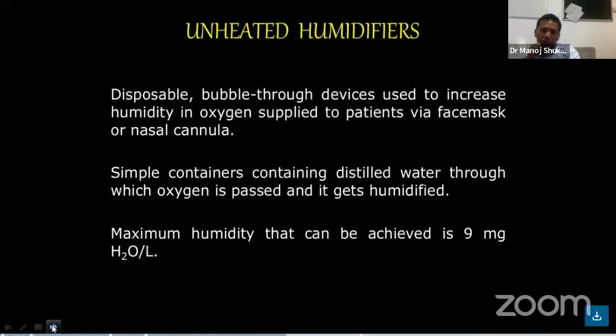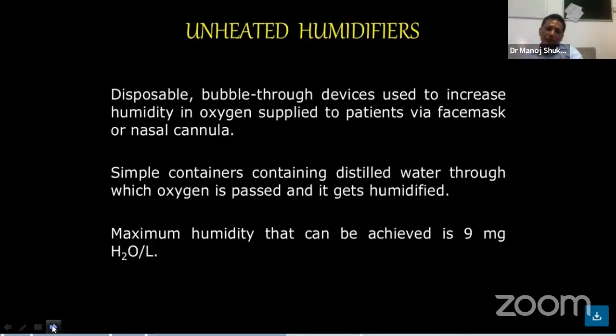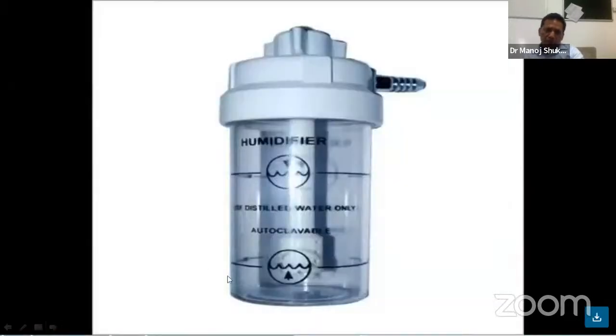The second type is the unheated humidifier. It is a disposable bubble-through device used to increase the humidity in oxygen supplied to the patient while using a nasal cannula. It simply contains distilled water through which oxygen passes and gets humidified. The maximum humidity that can be achieved is around 9 mg H2O per litre. This unheated humidifier is used in recovery units and sometimes in other patients.